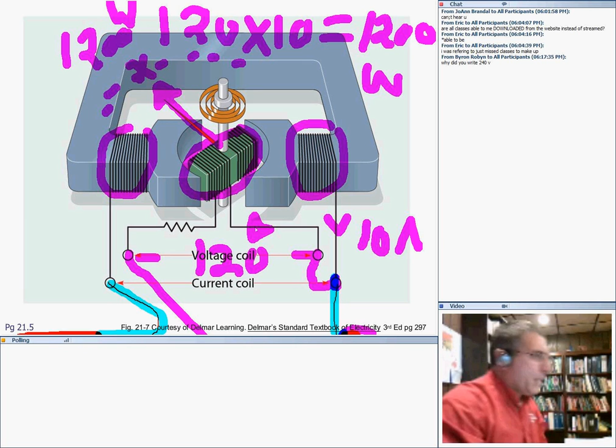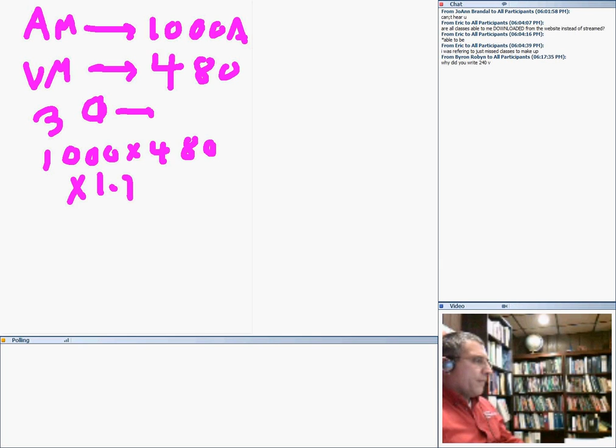I know you have a lot of equipment. I don't have a wattmeter, but I can calculate it using the voltage and the current. If I have an ammeter and go to my panel and read 1000 amps, that's easy, slap on a meter and get about 1000 amps. Then with a voltmeter I read 480, and this is a three-phase system. So I do my math: take 1000, multiply by 480, then multiply by 1.73 because it's a three-phase component. This amount here would be the power in volt-amps. This is not the watt. The only thing missing is the power factor.